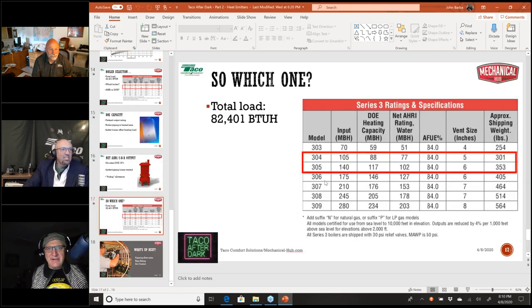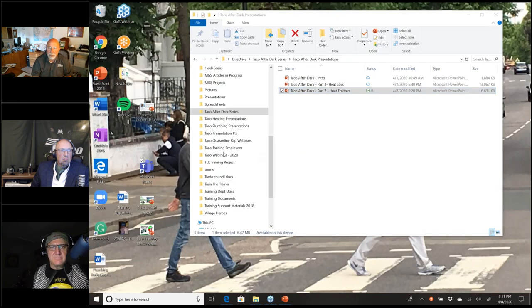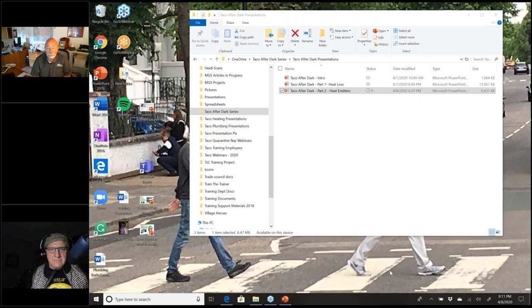Here we go. Down at the bottom here, it should tell you for this particular boiler, all models are certified for use from sea level to 10,000 feet in elevation. Outputs are reduced by 4% per 1,000 feet above sea level for elevations above 2,000 feet. So you reduce that output by 4% every 1,000 feet above 2,000 feet. Normally your modulating boiler companies will be somewhere around half of that, so 2% per 1,000 foot after 2,000 foot. Again, check with them. It's in writing. You've got to get it from them, but that's generally the rule.